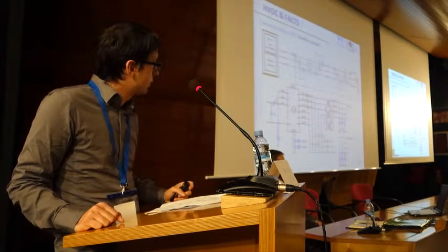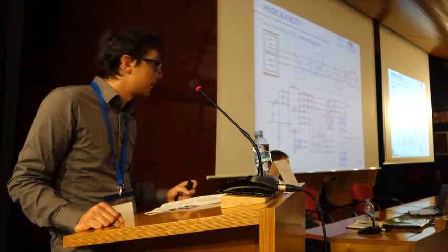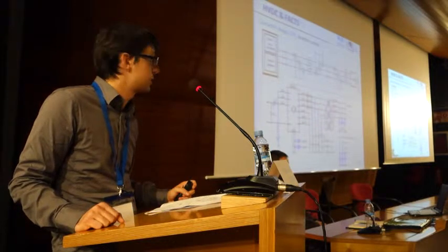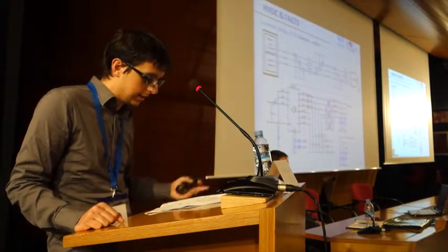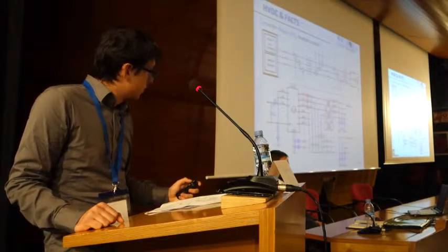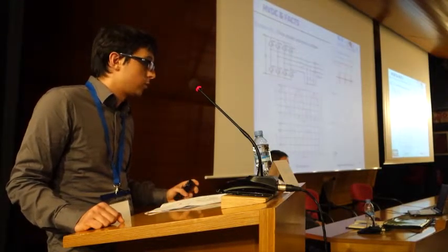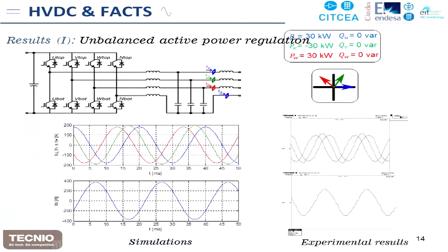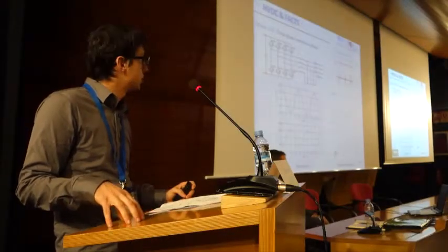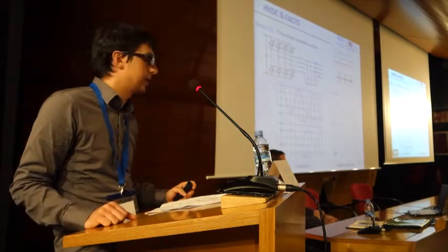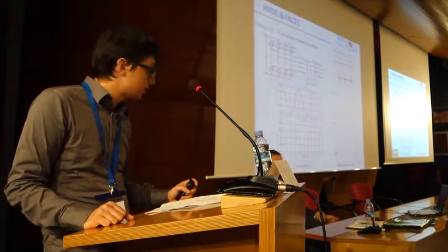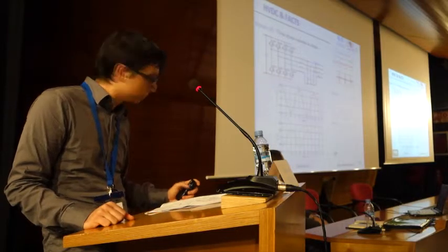And we then use again another structure of proportional resonant controller. We have now the voltage that we want to synthesize, and using a modulation strategy, we get the shoot signals for the converter. So, starting with the results, we are going to present basically six scenarios. 2 of them are related with the grid-connected mode, 2 of them regarding the transitions between the grid-connected mode and the islanded mode, and 2 more focused on how we want to handle the short circuits in the island operation mode. In this case, the first scenario is an unbalanced active power regulation.